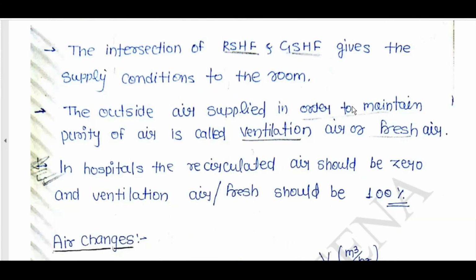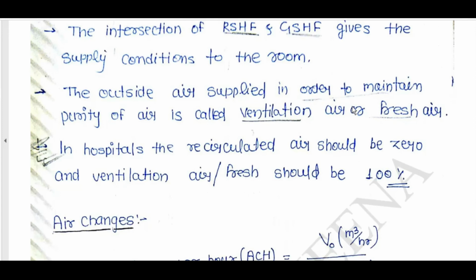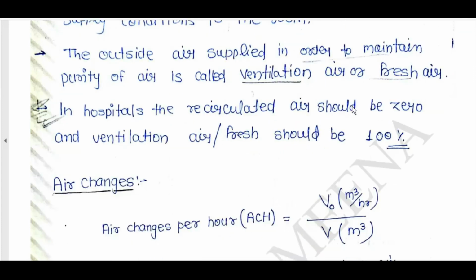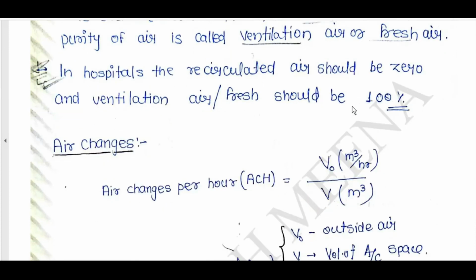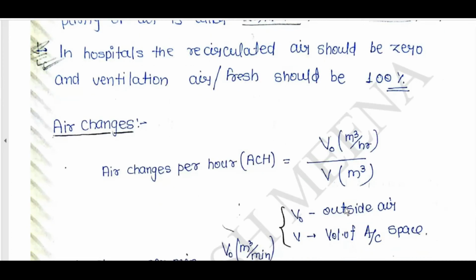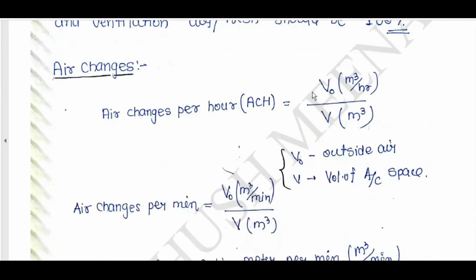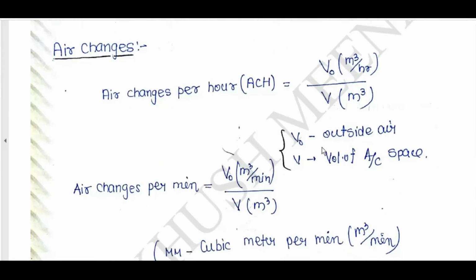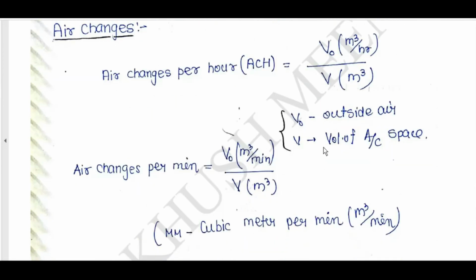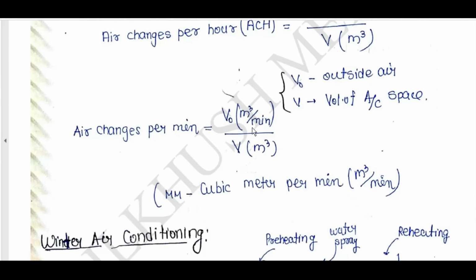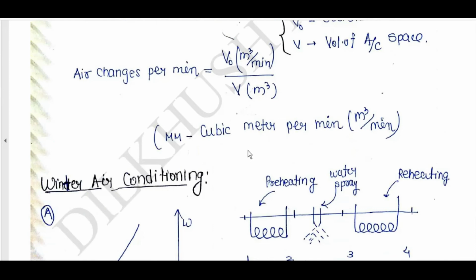The outside air supplied in order to maintain purity of air is called ventilation air or fresh air. In hospitals, recirculated air should be 0 and ventilation air or fresh air should be 100%. Air changes per hour, ACH, is equal to VO by V. VO is in meter cube per hour, V in meter cube. VO is outside air, V is volume of AC space. Air changes per minute is equal to VO meter cube per minute by V meter cube.